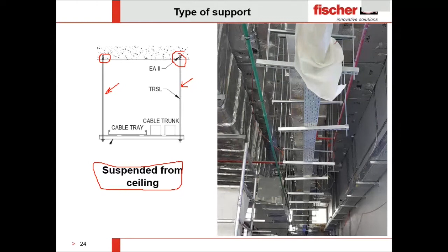So when we have very high loads like this, we should not take the risk of putting all these layers, all this load, on one anchor. Imagine if one service only fell down, it will work like a domino—all the MEP services will fall down. And it is much, much more expensive to repair than to just invest in this system. So in this case, contractors prefer to go to wedge anchors, meaning bolt anchors, which can easily be installed in the concrete and be safer for these high loads.